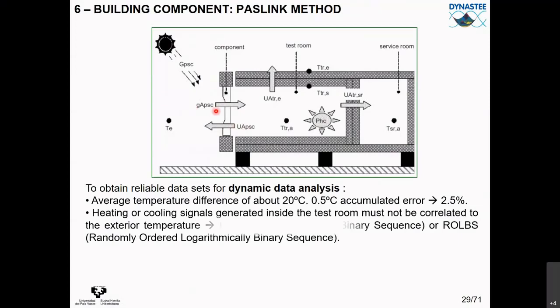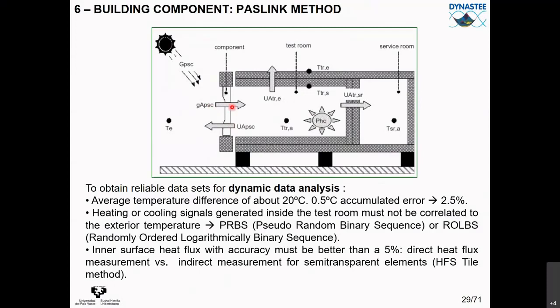You can measure exterior temperature, interior temperature, produce a heating input to create a temperature difference, measure solar radiation, and measure all heat flow through all walls except the component being characterized. We want to obtain the UA value and solar aperture of this component. The idea is to produce a large temperature difference between interior and exterior — once we have a big temperature difference, the error in that measurement is small. We produce a heating signal with specific characteristics to make parameter identification of UA and solar aperture easier.